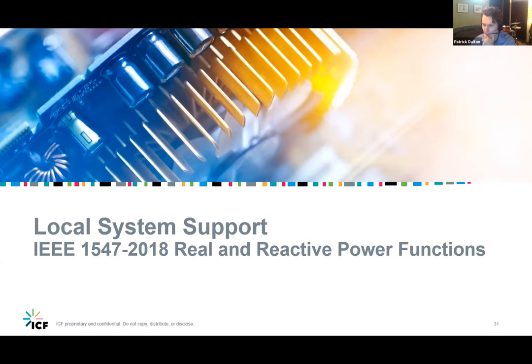There's a lot there. I guess I would say that the difference between DER with load and dedicated power generation is going to often affect that reference point of applicability, either being at the grid interface or the DER device or system interface, and that will affect how the system's required to respond to certain events. But in terms of open phase and anti-islanding, those are requirements of all DER. They're required to detect and respond to those types of conditions. So I'm not sure that entirely answers the scope, but if there were specific parts of that, I'd be happy to go into a little bit further detail.